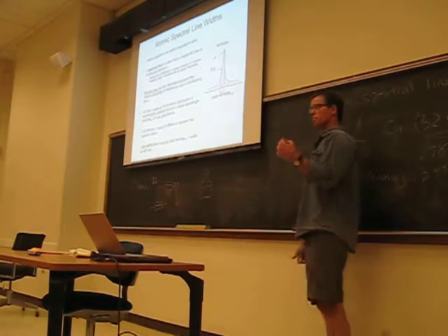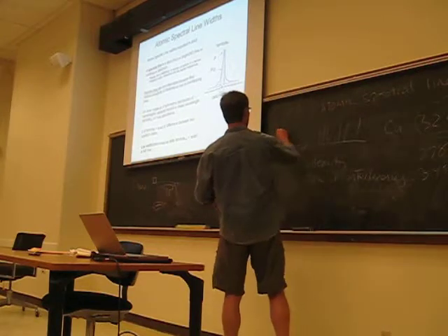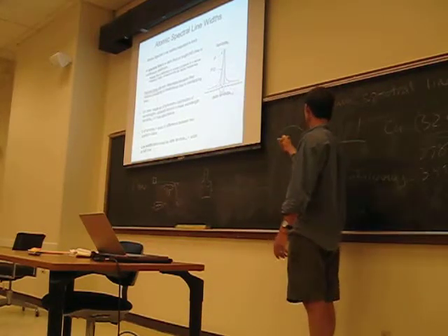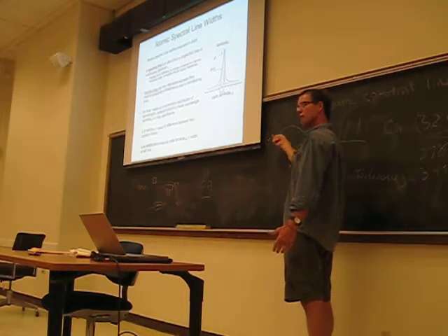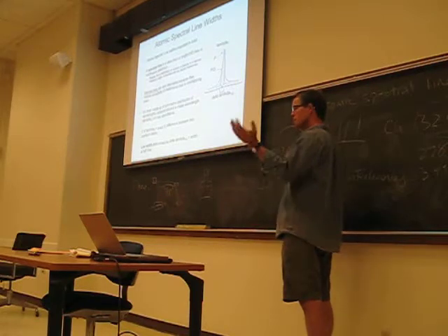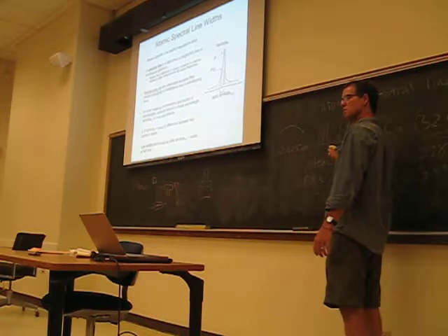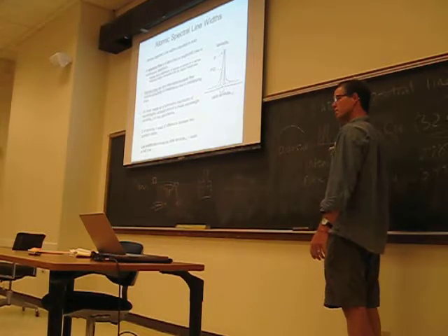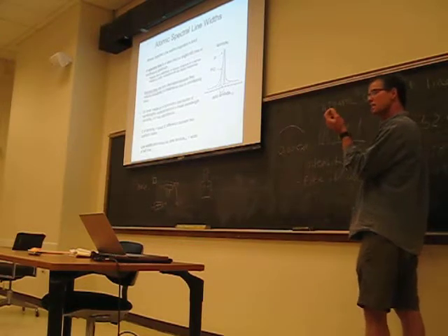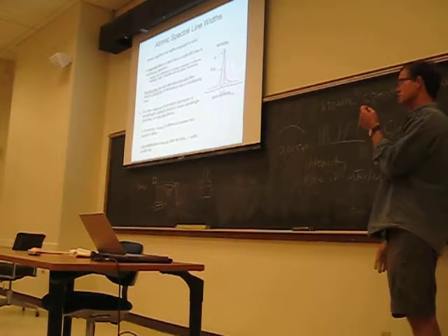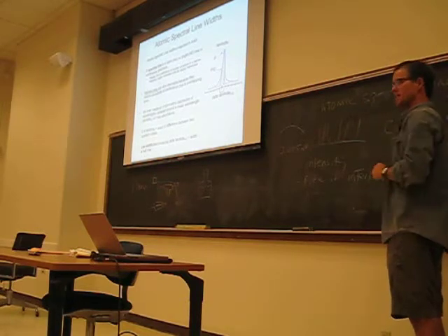And in molecular absorbance, when you were doing a wavelength scan, you saw something that looked like that, right? Over the course of 100 nanometers, probably, right? And so it's a very broad absorption line of your copper ligand complex. In comparison to the absorption spectral lines for atomic absorption, they're extremely narrow, right? Very, very narrow. And the advantage of being more narrow is that it can be more selective for exciting only the copper atoms, in this case, that are going to absorb that incident photon because it matches the quantum of that energy exactly.